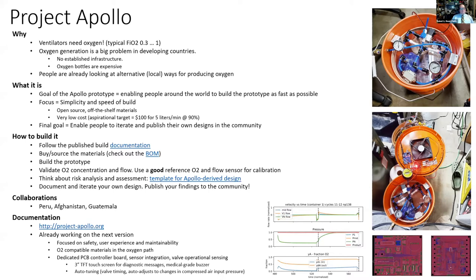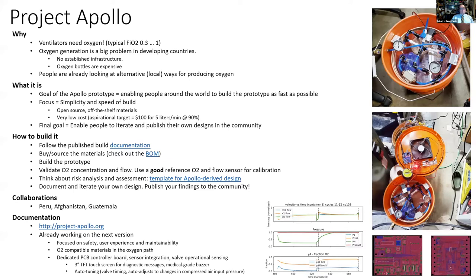Do you want a VentMon device which measures oxygen concentration, flow, and pressure? We are looking at various options. Someone is developing a number of sensors — one uses a $15 sensor from China which measures concentration to 0.1% and also measures flow up to 10 liters per minute. The goal for the whole thing is $100, so if you can get an even cheaper sensor, I'm happy to take a look.